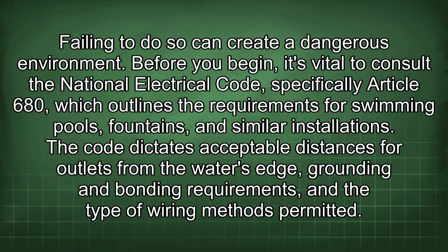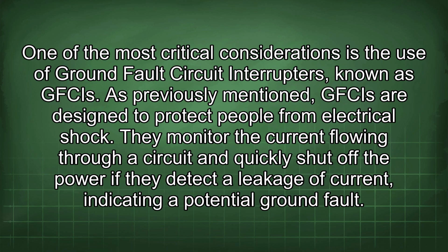Before you begin, it's vital to consult the National Electrical Code, specifically Article 680, which outlines the requirements for swimming pools, fountains, and similar installations. The code dictates acceptable distances for outlets from the water's edge, grounding and bonding requirements, and the type of wiring methods permitted. One of the most critical considerations is the use of ground fault circuit interrupters, known as GFCIs.